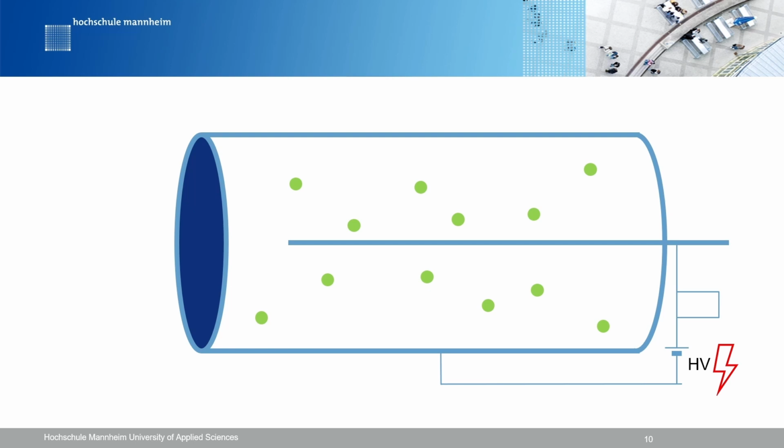The Gamma Scout is utilizing a special type of GM tube with an end window which is built from a low-density material, for example mica, which is permeable for alpha and most beta particles. If an alpha or beta particle passes through the window, it starts interacting with the gas, promptly ionizing its particles. Gamma rays need to interact with more dense materials, like the body of the tube.